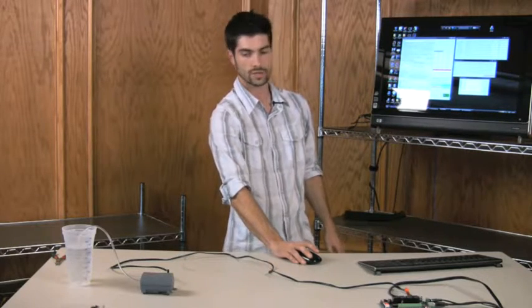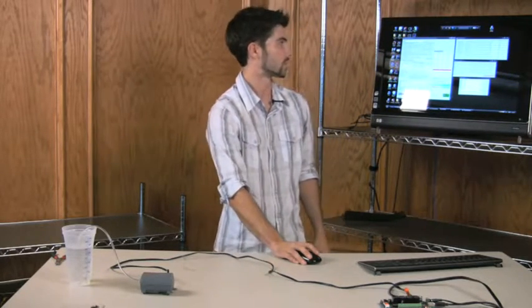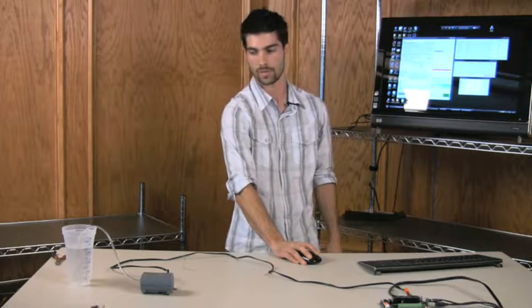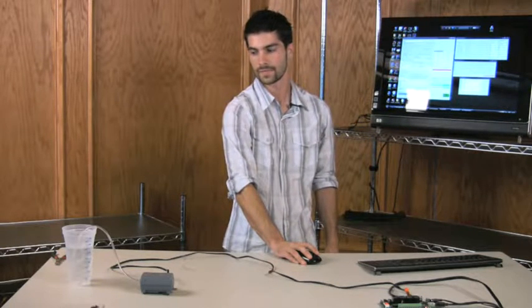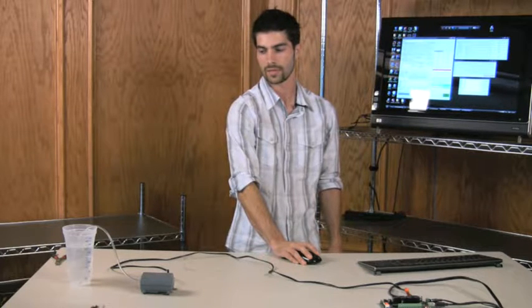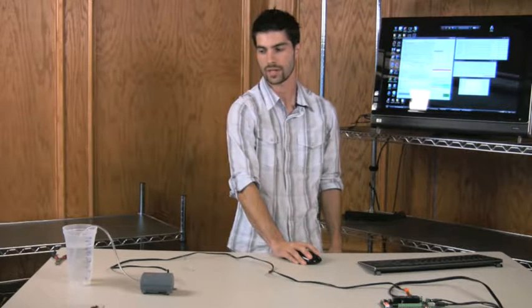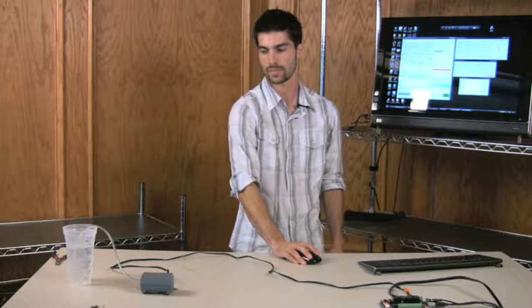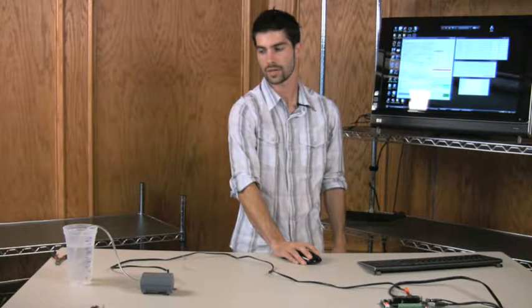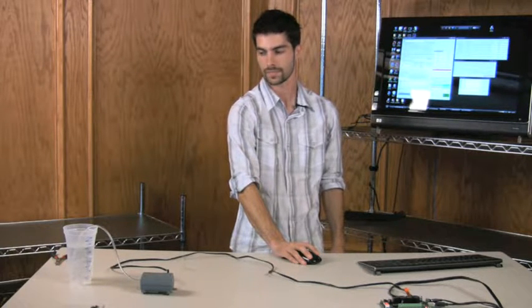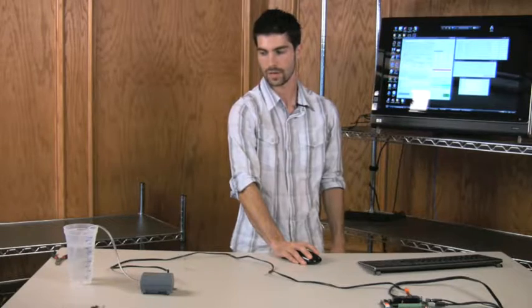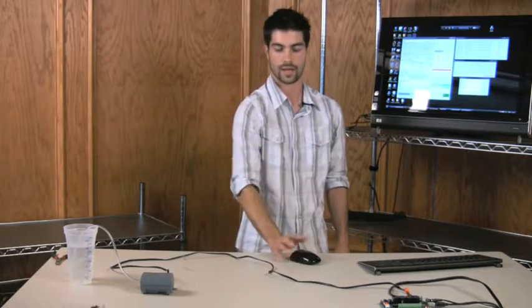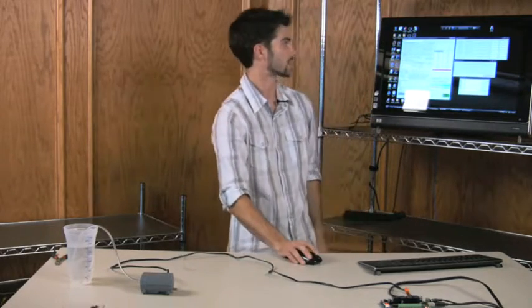Now let's try relay four and let's see if we corrected our problem with our induction. Seems to be working, switched on and off a few times. Make sure that we have in fact solved our problem. And it looks like we have. Okay, and that's how you fix induction with a capacitor.